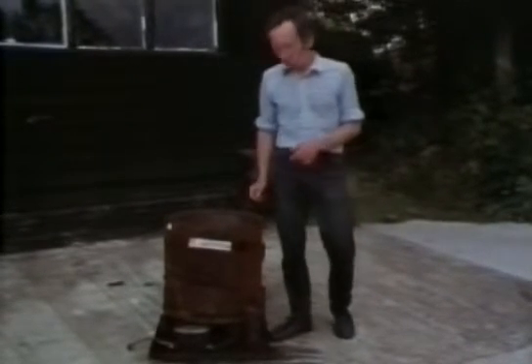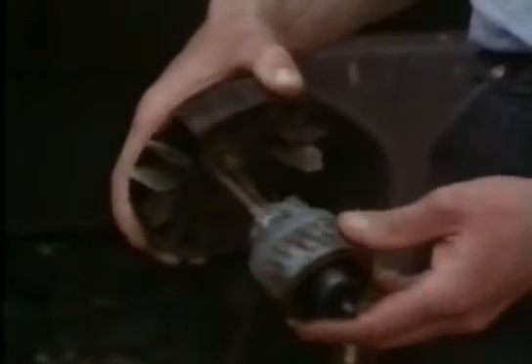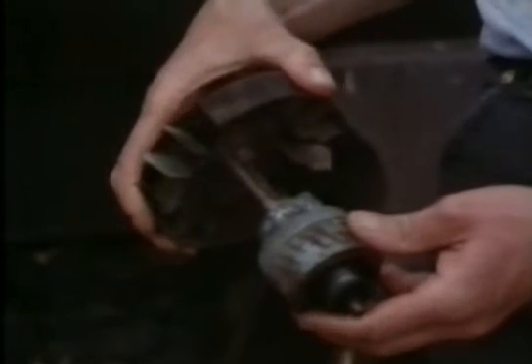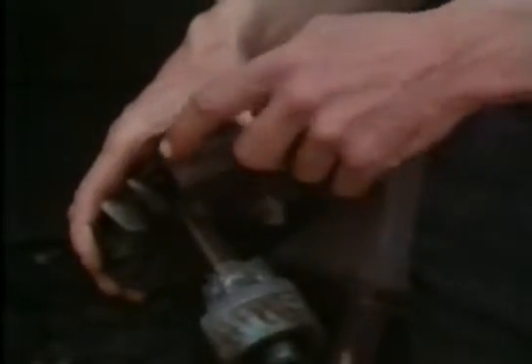This is the wall flame type, and the oil comes in right at the bottom under an electric motor. This is the shaft of the motor, and as it whizzes round and round, the centrifugal force pushes the oil outwards and upwards through these tubes, and it comes out the end as a fine spray. This spray is ignited by an electric spark.